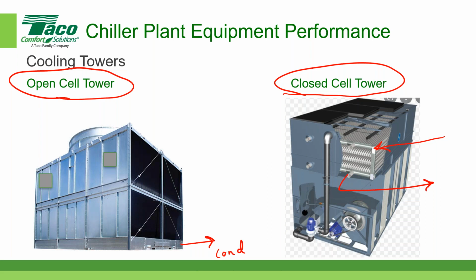So for the water that's used for evaporation, there's a little pump down here. The water is pumped up to the top of the tower and trickles down through this heat exchanger. So the water that comes in contact with the air does not mix with the water going out to the condenser. Closed cell cooling towers typically are used for relatively smaller applications. They're very popular, for example, for water source heat pump systems where you don't want the condenser water to be exposed to the atmosphere, which could be problematic, sending that water to tiny condensers in air as water source heat pumps.